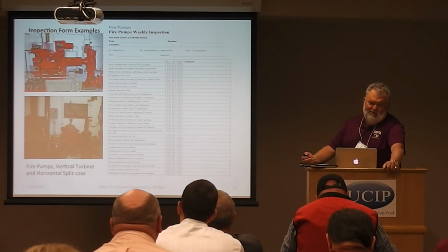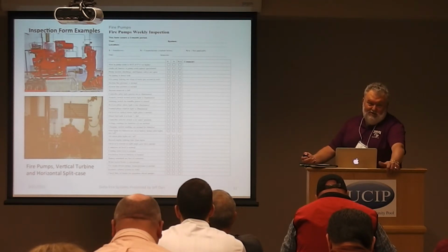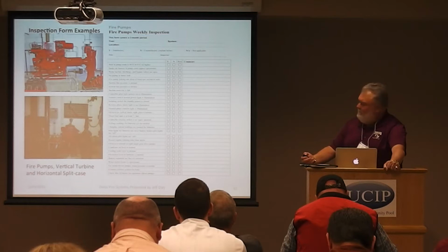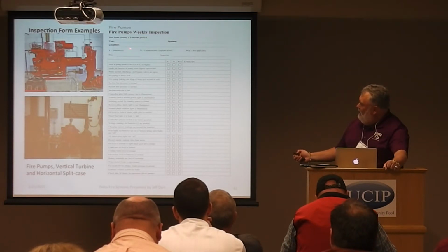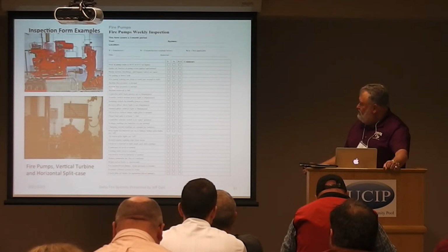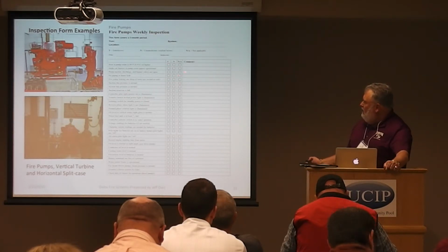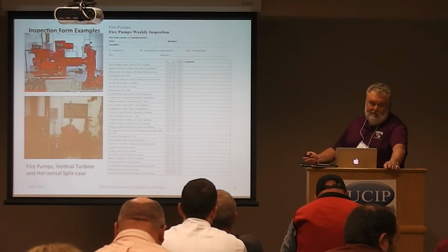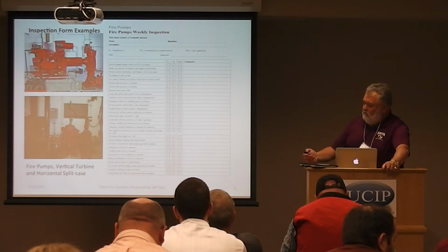One of the advantages of Utah is we have these high mountains around it. We have a lot of water pressure. So while we do have quite a few fire pumps, we don't have the number that other parts of the country do. But here again, it's broken up in pretty standard, easy to follow things. This is generic, so it's got both the diesel and the electric requirements in it. That's why you have a yes, no, or NA. And your personnel can do those weekly ones, monthly, no problem with those.